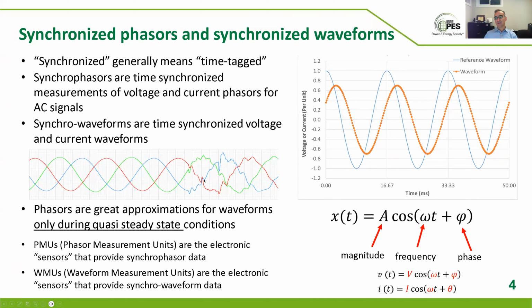And that's where synchro waveforms are a lot more valuable because they actually give you a lot more resolution, more of the truth. Data doesn't get lost in that compression. And each have their place. The nice thing with phasors is that there's less data to communicate relative to waveforms. A lot more data compared to SCADA, but a lot less relative to waveform. And therefore, the communication burden and those things are less, especially if you want to send it to far places. But at the end of the day, both synchronized phasors and synchronized waveforms are measurements that have time tagging so that you know when they were done, and they each have their own use.